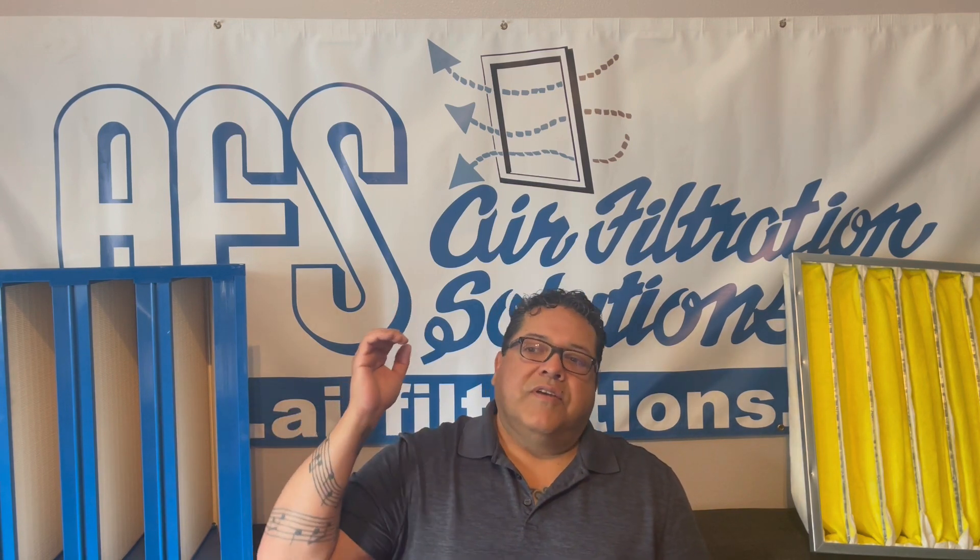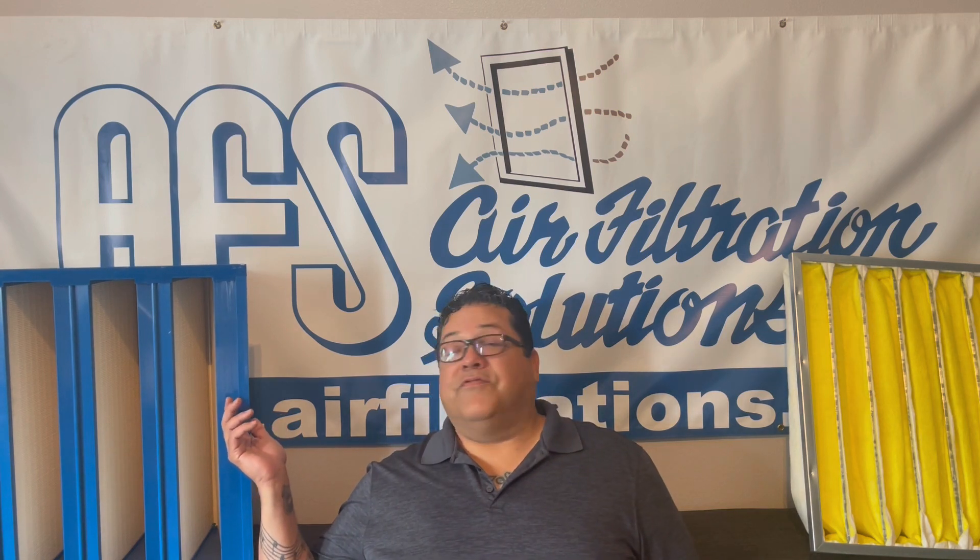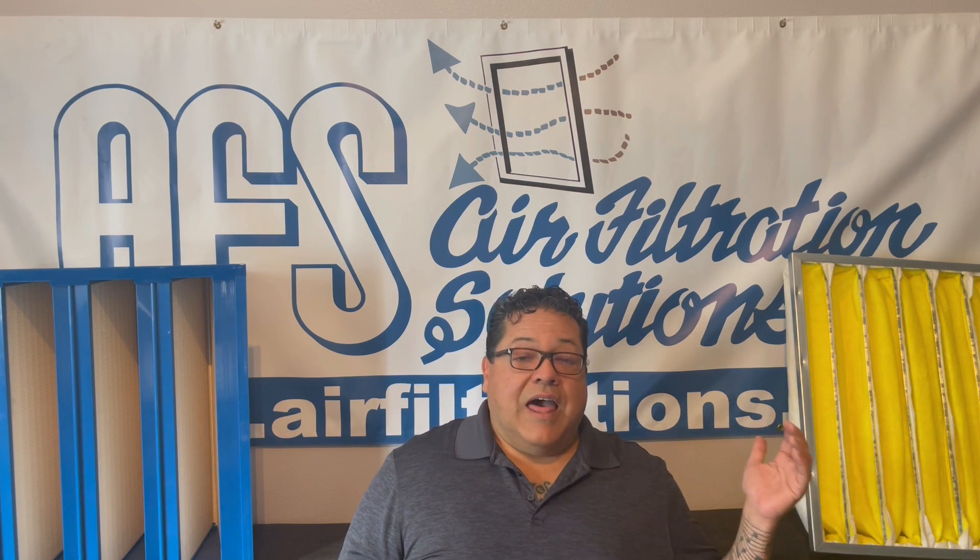Another very important factor is labor intensity. Some of these hospitals — Kaiser, for example — have hundreds of filters on the rooftop. You have to haul them through the hospital, get to the freight elevator, all the way to the top, then two flights of stairs. These bulky filters are 35 pounds apiece — hundreds of boxes. Versus these, packed three or four per box, significantly lighter. One box of three or four of these is probably half the weight of just one of those. A lot less boxes, a lot more manageable — I'd give fiber bond the advantage on labor intensity.